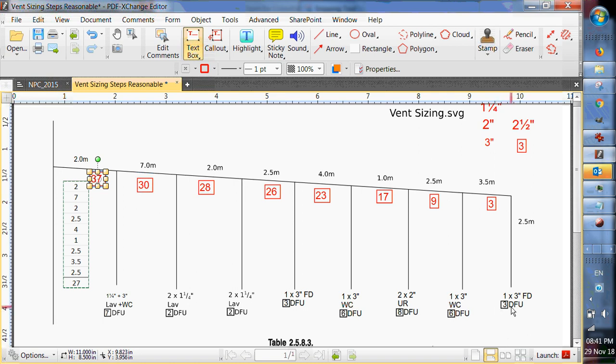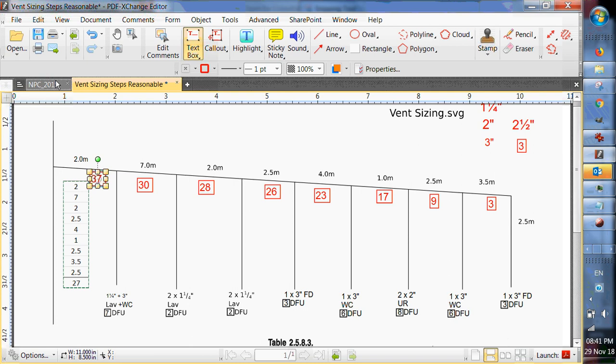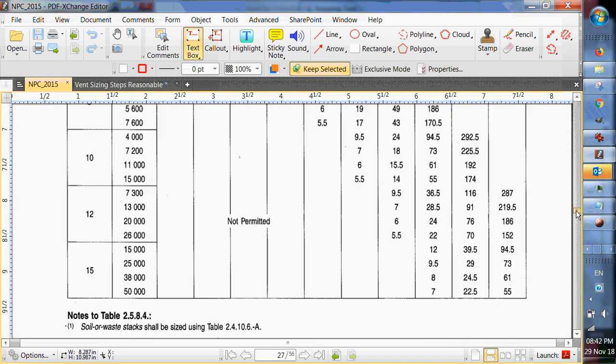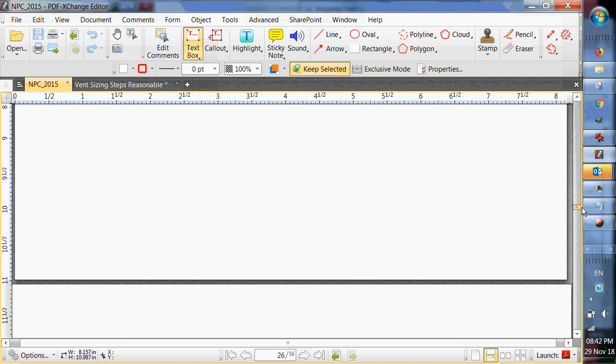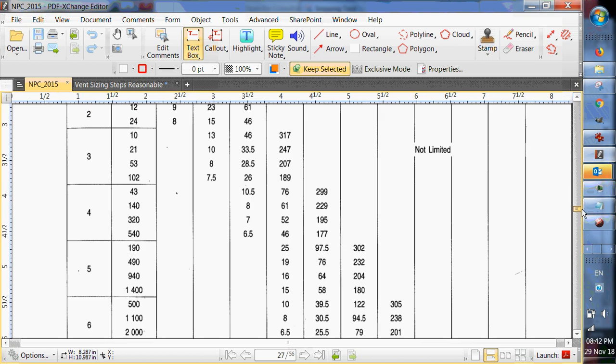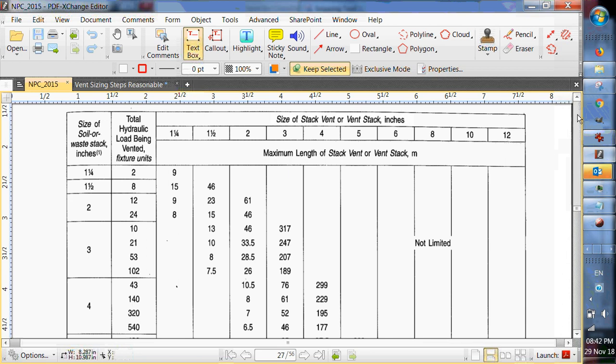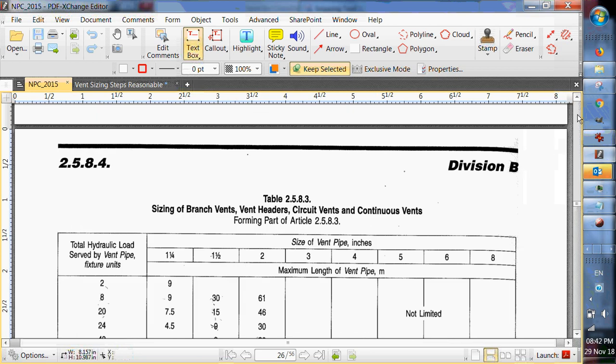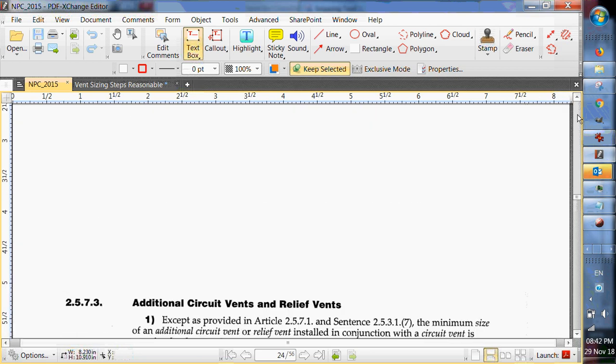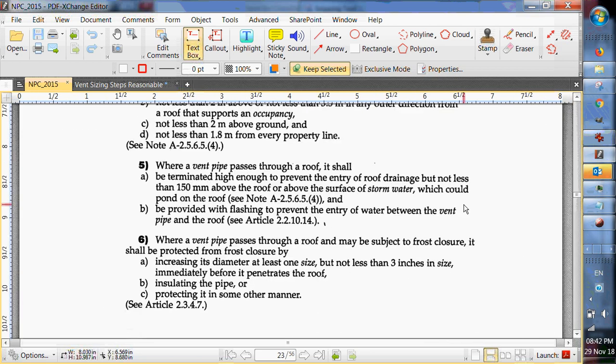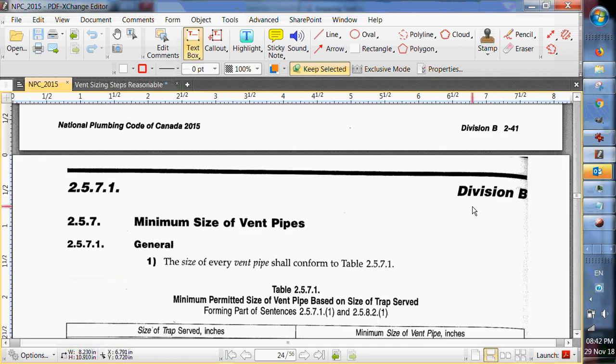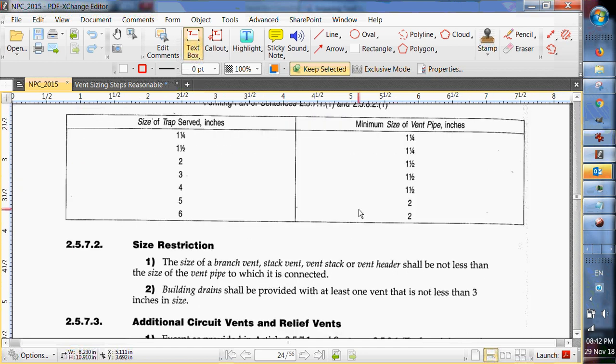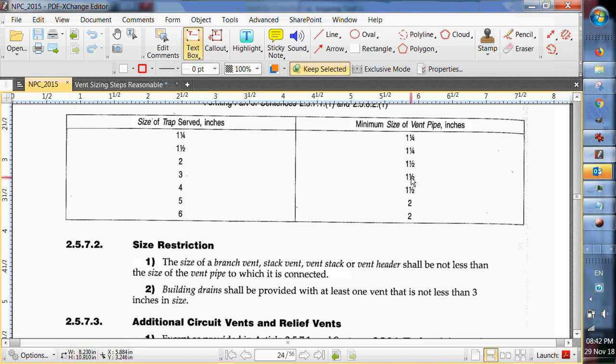Now I need to go and find out what the vent size is going to be for all these drains. So I'm going to go down into the 2.5 section. Stack vent is not the chart we want. We want the minimum size of traps here. So water closets and floor drains, three inch. They're all going to be one and a half inch vent.